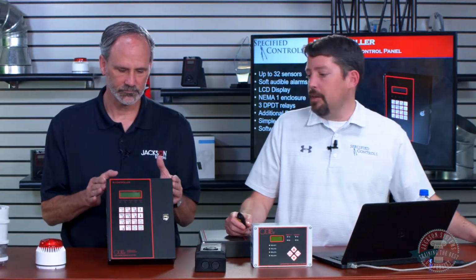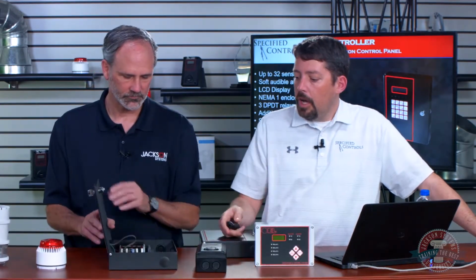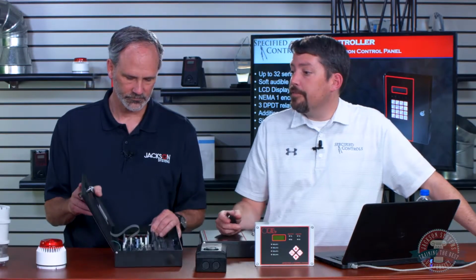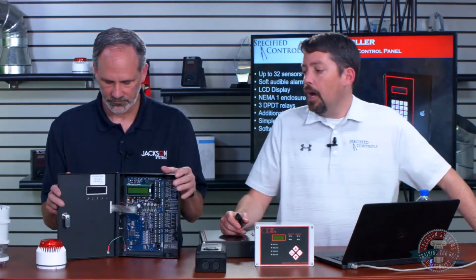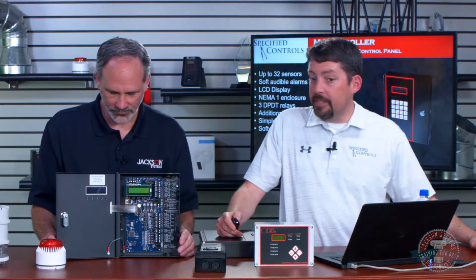The M controller, which is what we've been talking about the most, is most commonly used. I'd say 80% of the jobs we do, at least. One thing to think about with this one is that it is a NEMA 1 enclosure, which is good for most garages. It's a locking NEMA 1 enclosure versus a NEMA 4 enclosure. So there are concerns if it is in an environment where it could get wet or gunky. Put it someplace else if there's a concern about the environment it's in.